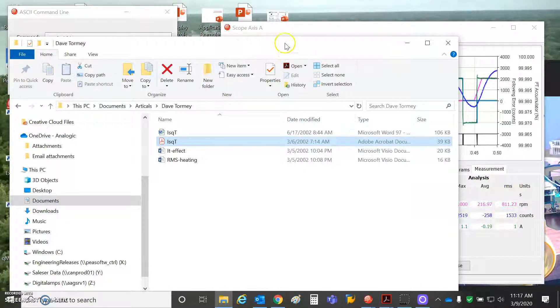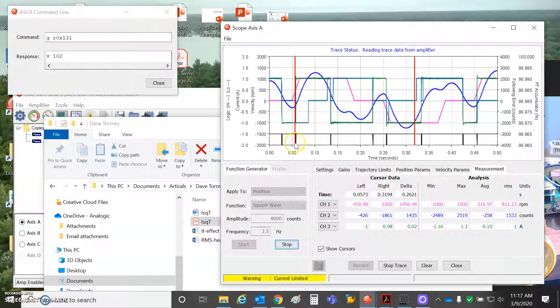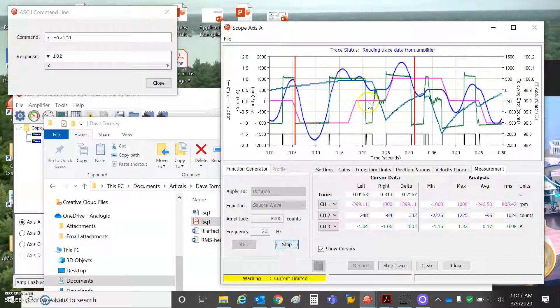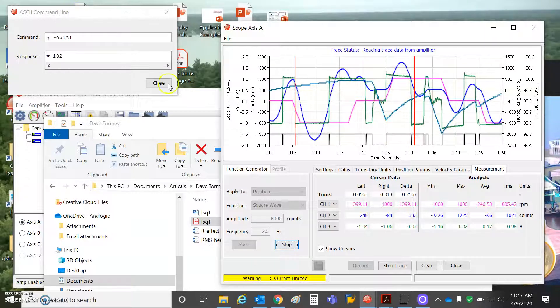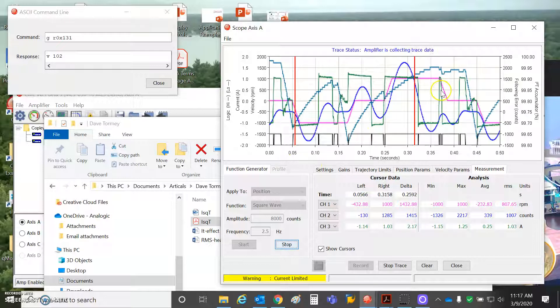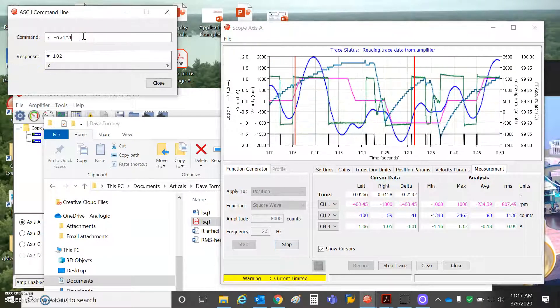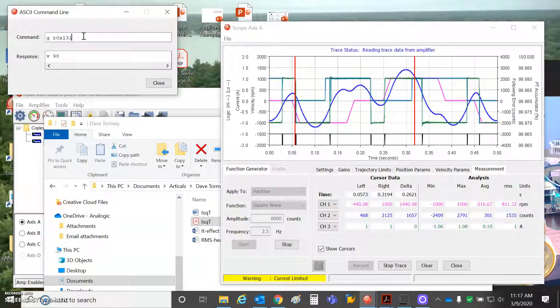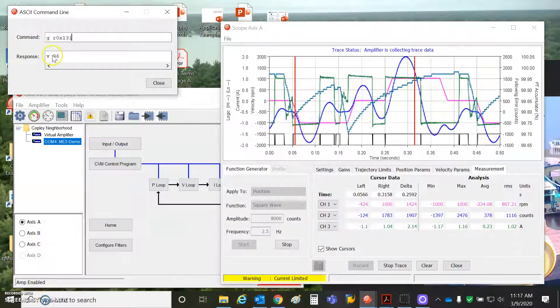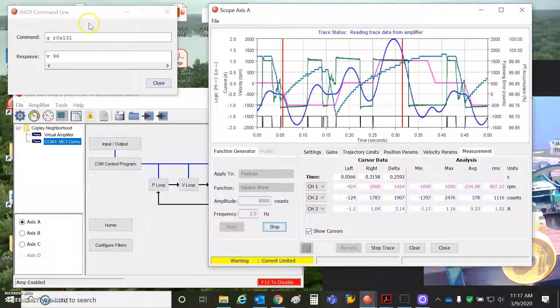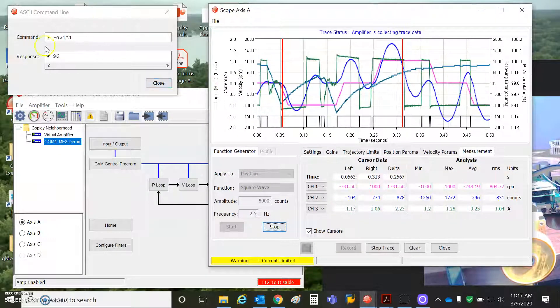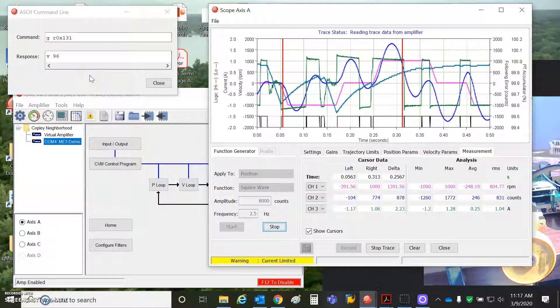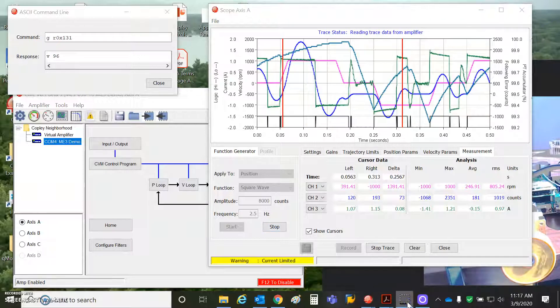What it's not doing is preventing us from having problems with, if you're at a continuous current limit constantly, your following error, your motion profile suffers. And eventually you're going to get a following error under normal conditions. And again, we're current limiting constantly and our RMS current is at an amp. And so that's the danger zone right there. So we can use this function or this feature in the drive to preempt something bad happening.